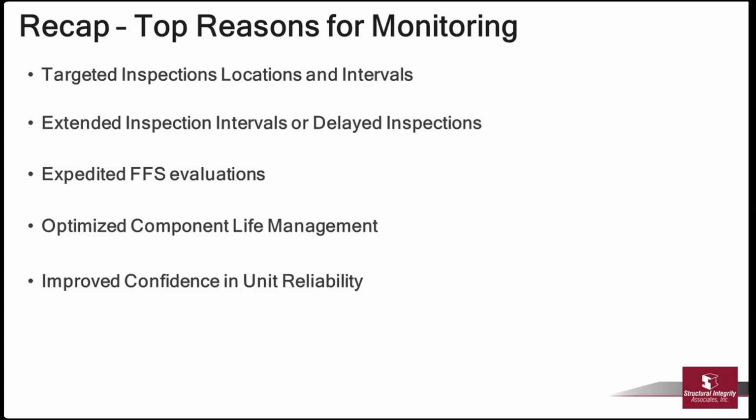So the spray-on, that's a ready for prime time product at this point? Definitely. I've got another slide in a different presentation, but for a different plant, we've been monitoring with spray-on transducers for 3+ years now. What we're working towards is the linear phased array approach to eventually one day be able to monitor cracks.